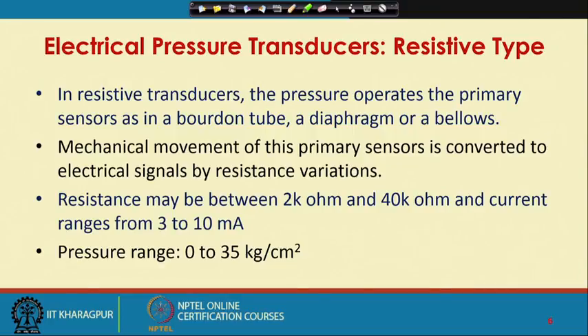Next, let us talk about resistive type electrical pressure transducers. We talked about inductive type, now we will talk about resistive type. In resistive transducers, the pressure operates the primary sensors as in a Bourdon tube, a diaphragm or a bellows. Mechanical movement of this primary sensor is converted to electrical signals by resistance variation. So, here the electromechanical displacement transducer works on the principle that the resistance will change. We will measure the displacement by measuring the change in resistance. Resistance may be between 2 k ohm and 40 k ohm, and current ranges from 3 to 10 milliampere. The typical pressure range is 0 to 35 kg per centimeter square, an indicative range.